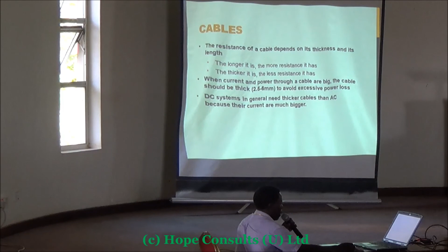When current and power through a cable are big, the cable should be thick. I gave here 2.5 millimeter, even more. DC systems in general need thicker cables than AC; we mentioned this and saw the reason why—it is because of the current. When you look at the effect of sizing on power loss, on your right that was A, and this was B. You can see how B can enjoy while A is really struggling to get it through.